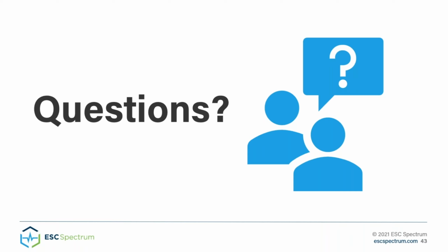The next one we have, it says, just to be clear, this is used to only get data out of StackVision, or is it used to get data into StackVision as well? That's a great question. I tried to show that it's a specific scenario where you're pulling information from another server into the StackVision server, but the StackVision server can act as an OPC UA server and receive requests from another server to pull data from the StackVision server. So you have that option, but the most common way I've seen it used is we're pulling information from another server. And the examples I showed demonstrated pulling information from a simulation server.